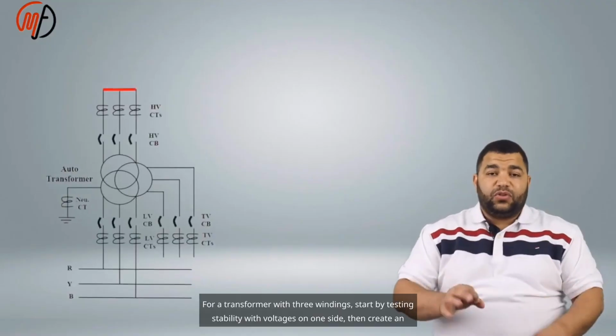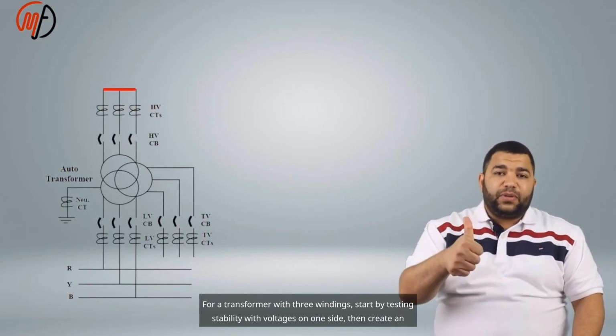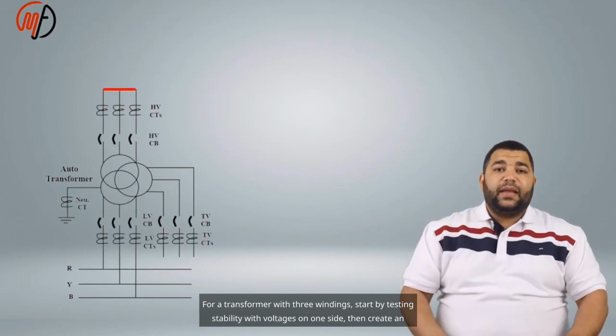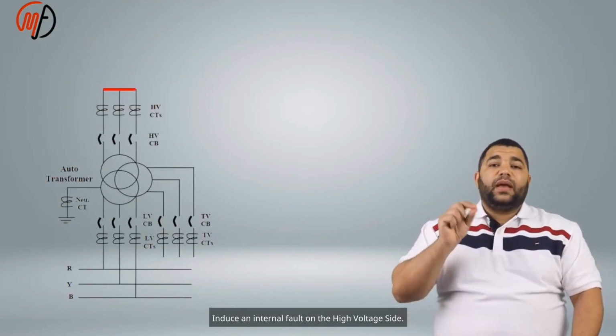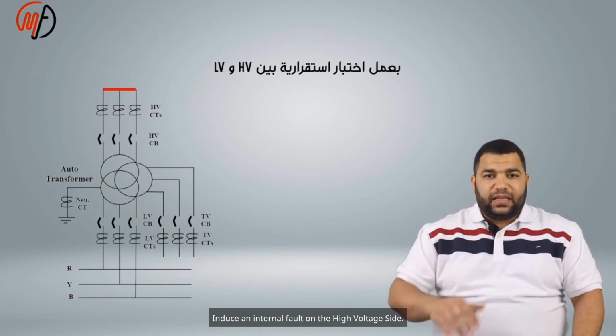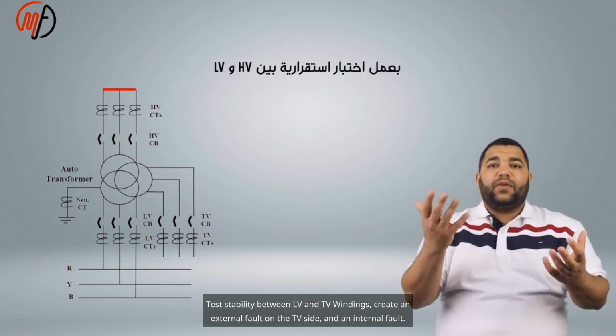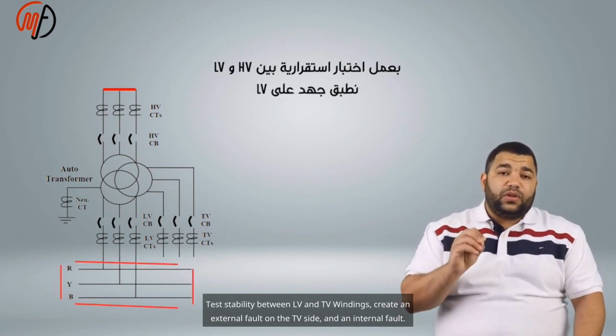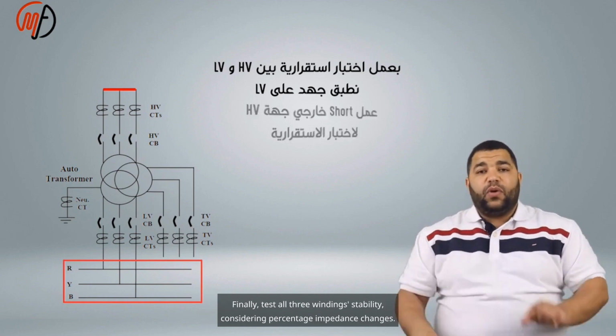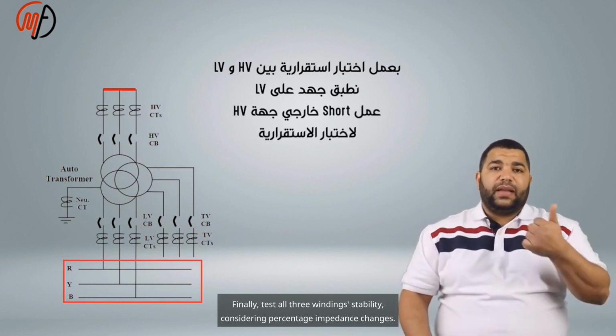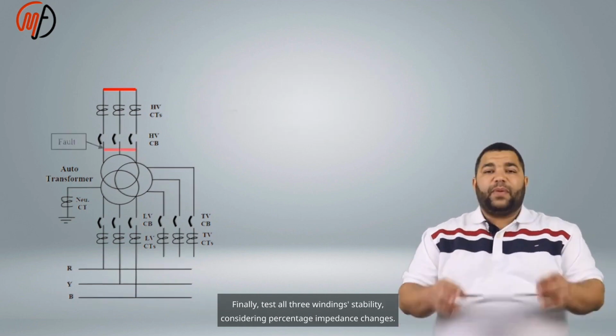For a transformer with 3 windings, start by testing stability with voltages on one side, then create an external fault. Induce an internal fault on the high voltage side, test stability between LV and TV windings, create an external fault on the TV side, and an internal fault. Finally, test all 3 windings stability, considering percentage impedance changes.